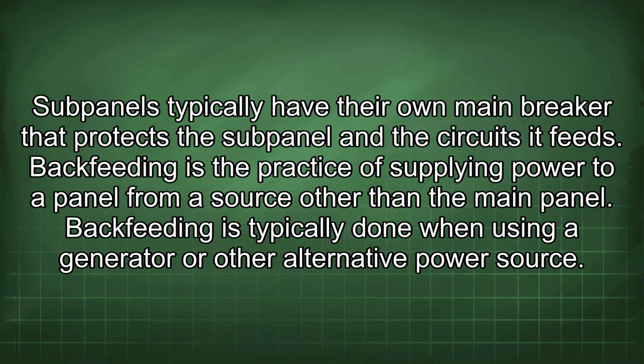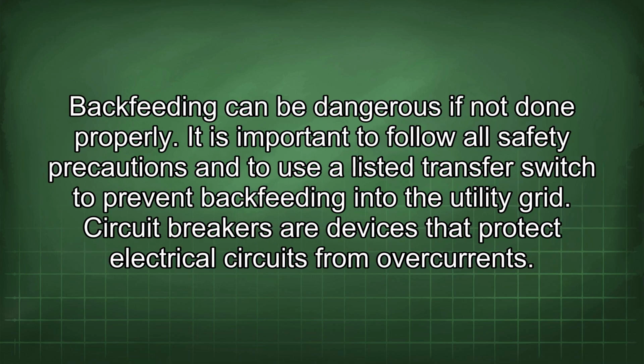Backfeeding is the practice of supplying power to a panel from a source other than the main panel. Backfeeding is typically done when using a generator or other alternative power source. Backfeeding can be dangerous if not done properly. It is important to follow all safety precautions and to use a listed transfer switch to prevent backfeeding into the utility grid.